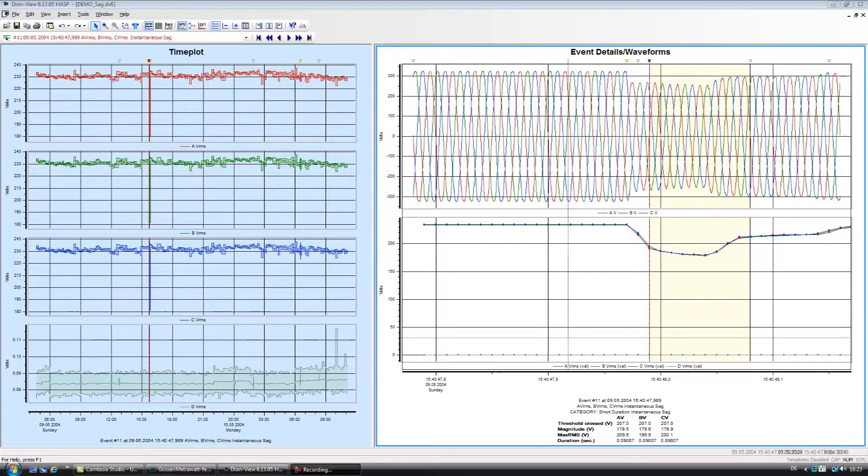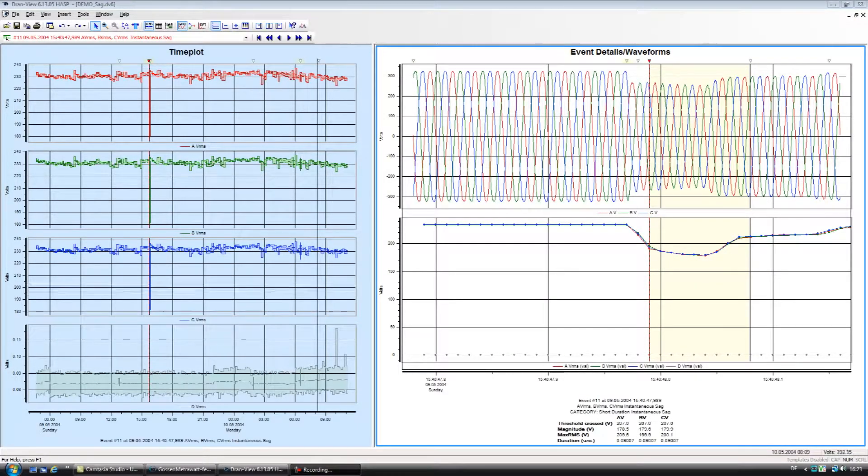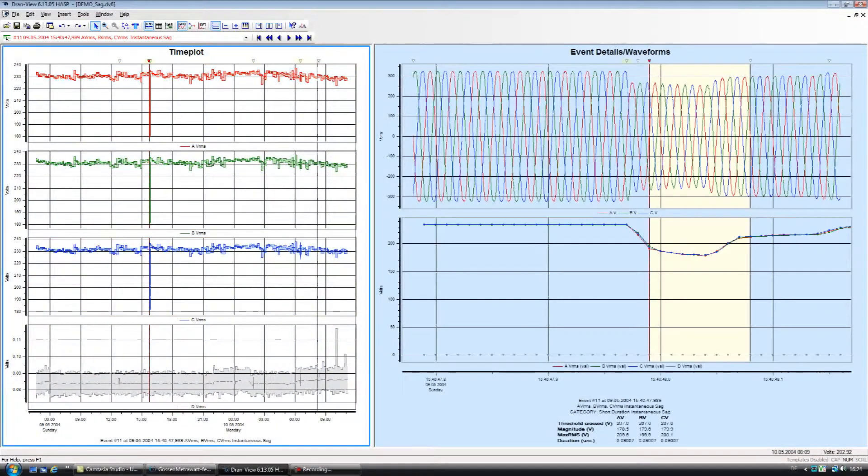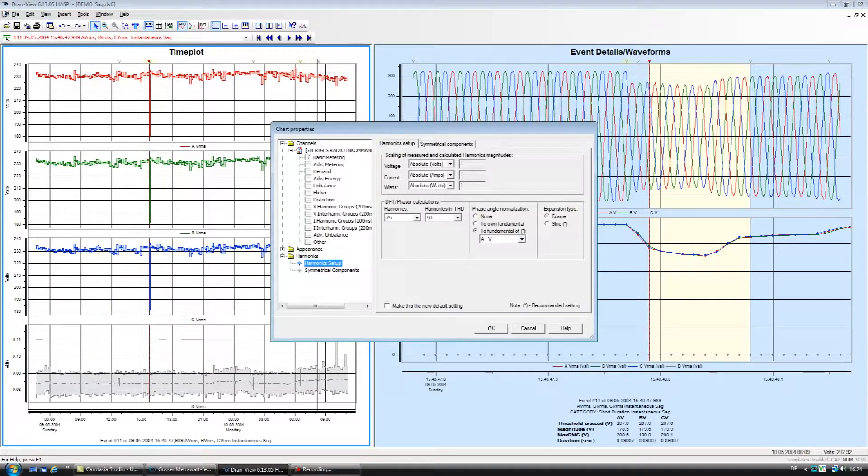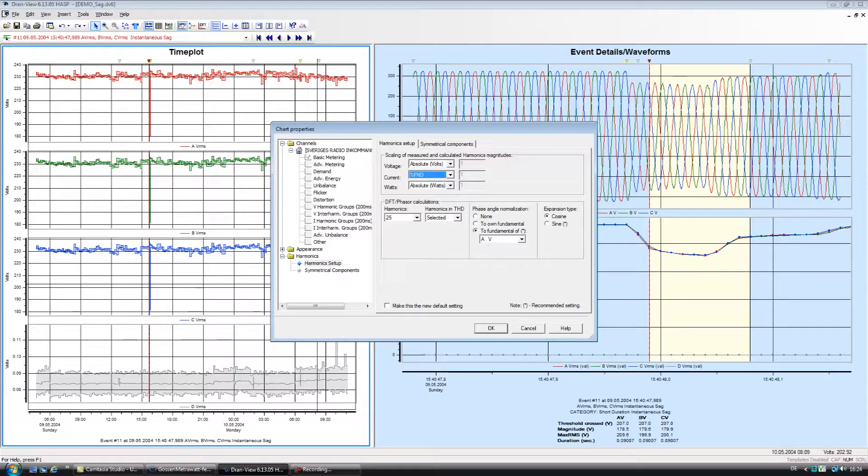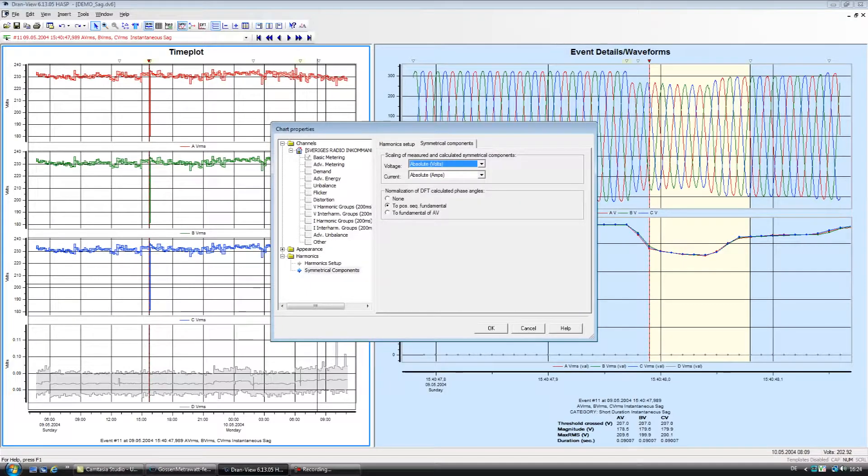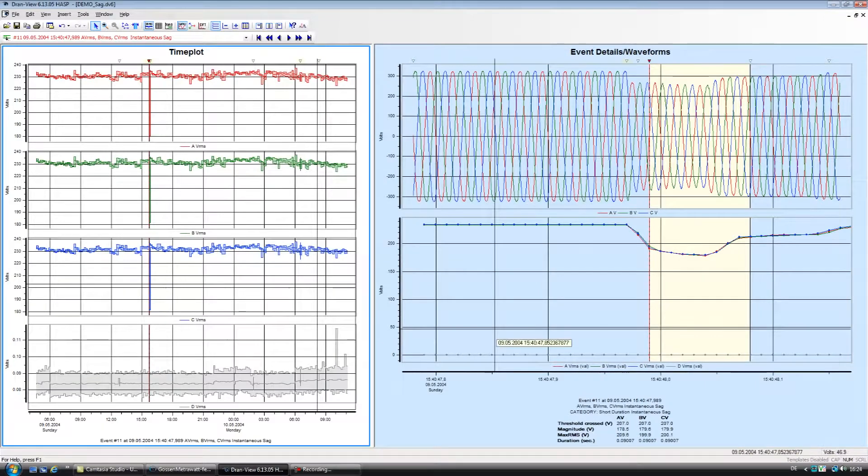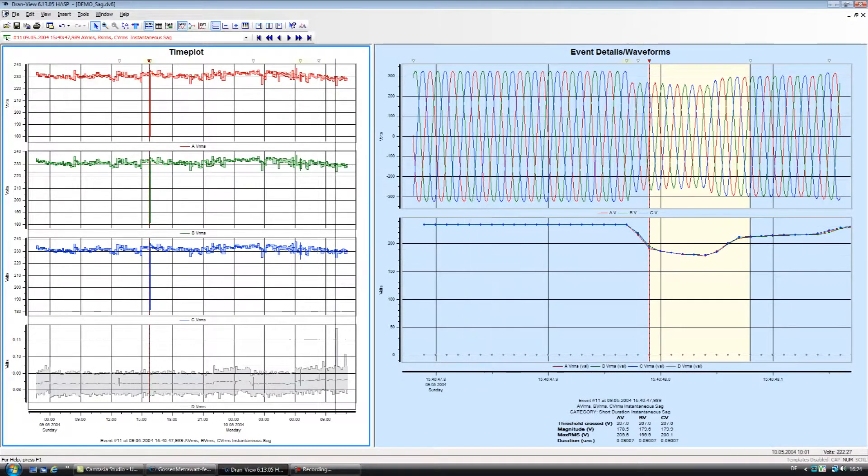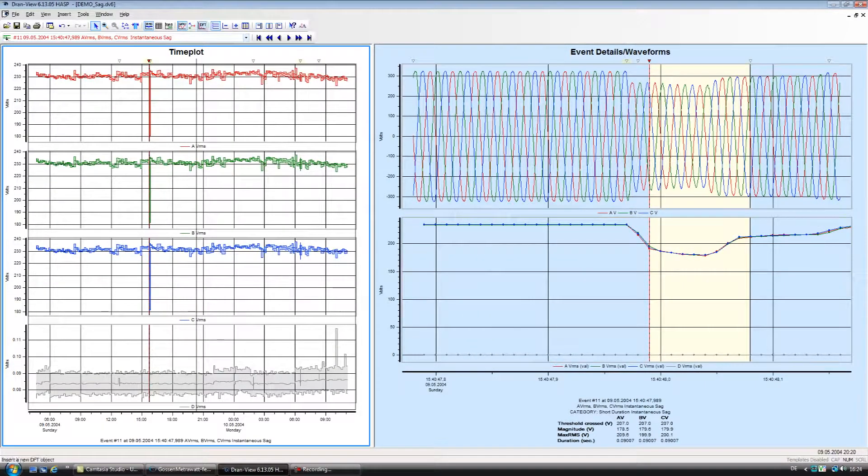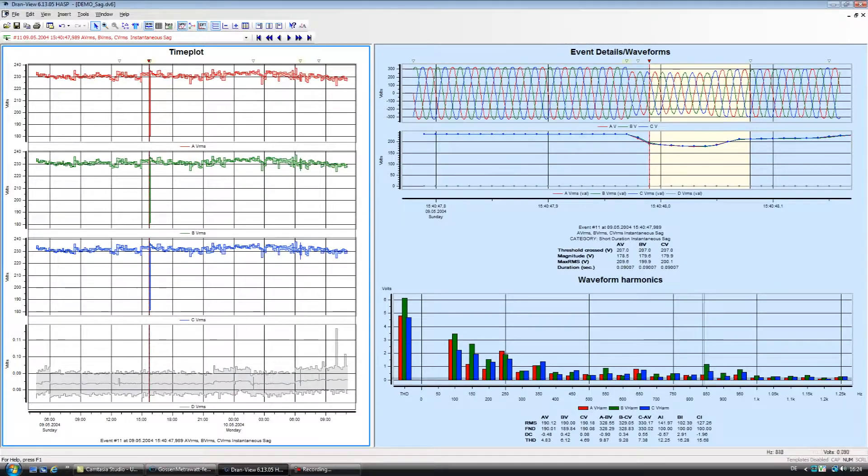Harmonics. Dran-View has some powerful capabilities for harmonic analysis. Being a data viewer, Dran-View displays trends and details of any harmonic information recorded by the instrument, such as THD, symmetrical components, k-factor, individual harmonics and more. On the other hand, Dran-View software is capable of snapshots that calculate harmonics and display them as a spectrum diagram, and with just one click.